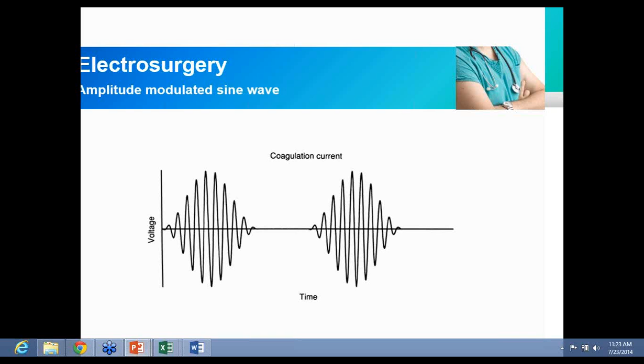If you notice at the very left-hand side, there's a negative going pulse, and then it's slightly longer than the next pulse, which is positive, and then the next positive pulse is even larger, and then we go small negative, and then even smaller negative, then increase. What they're trying to do there is fulgurate the tissue. So they've greatly varied the pure sinusoidal waveform, and they've greatly varied a standard coagulation waveform to achieve a desired physiological effect that the surgeon is asking for.